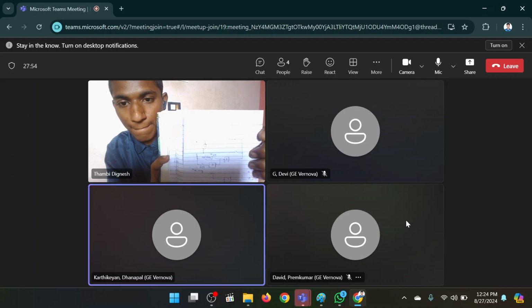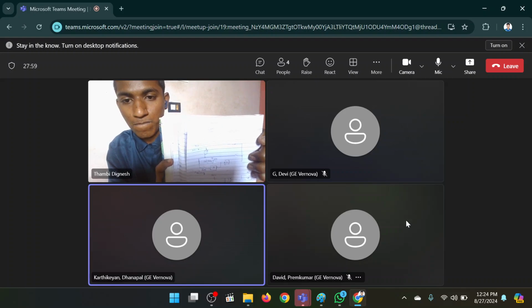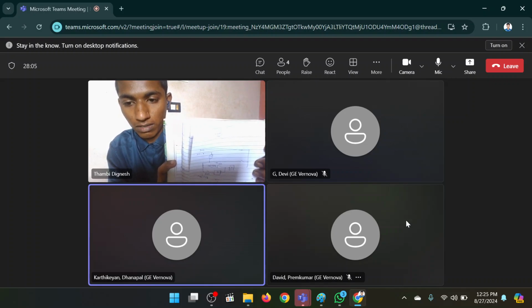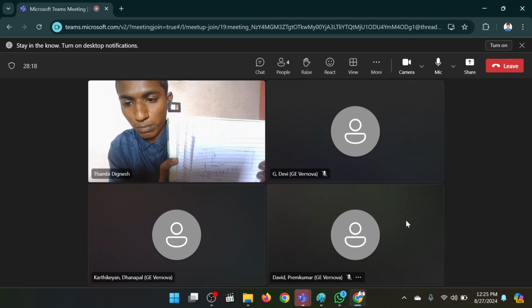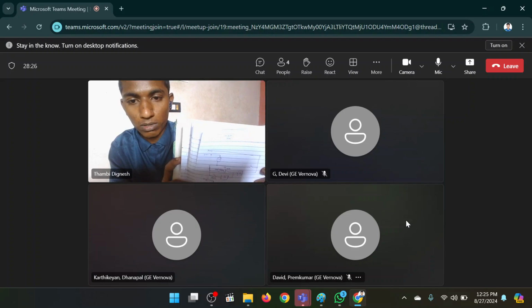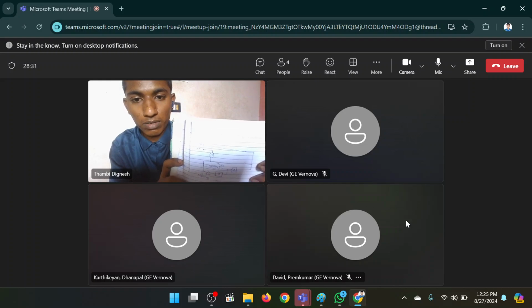So from the trip coil you are taking the negative, and through the contact you are giving it to one coil. So what will you call this coil? We are having two coils, right? Sir, A and B, relay one coil and relay two coil. No. What is the name of the two coils? Because the C coil will continuously monitor A and B. Yes, sir. What is the A coil? What is the B coil? Sir, during post close or CB closed condition, A will monitor the CB coil supply. During post close or CB in open condition, the B coil will monitor the supply for the CB.